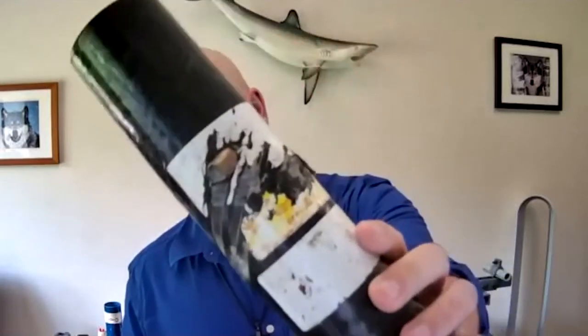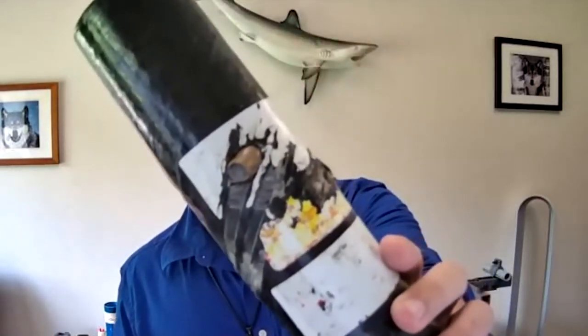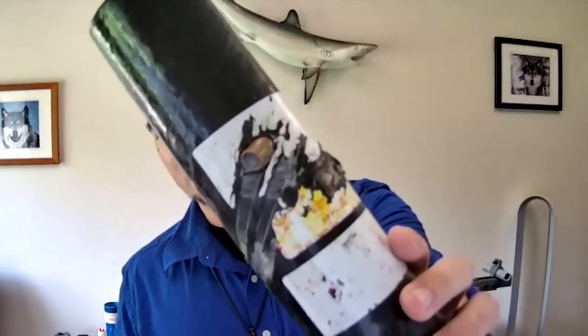We also have a Class 1 Div 2 conduit, which is referred to as a HAZDUCT or bullet resistant conduit. And when we say bullet resistant, we're not being facetious. As you can see from this example, it's a 45 caliber bullet embedded in our conduit from a distance of about 20 feet. This conduit will typically be used in very hazardous locations, wastewater to name one, or where additional rigidity or security for those cables would be required.